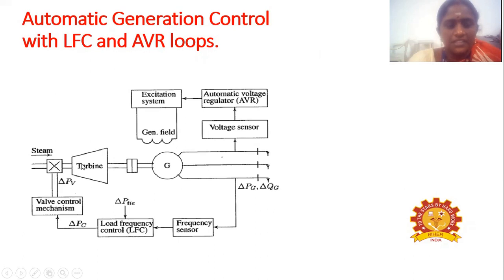See here, this is the steam turbine. Steam flows to the turbine through this valve. When steam enters the turbine, it starts rotating. When it rotates, the generator coupled to the turbine also rotates, cuts the flux and generates the voltage. So real and reactive power will be generated, and it is connected to the grid. Here we have to ensure the frequency and voltage are within the prescribed limits. For that, we sense the frequency using the frequency sensor and the voltage through the voltage sensor.